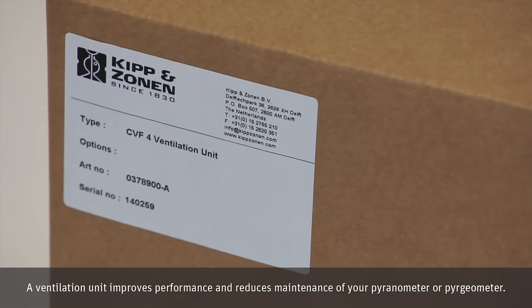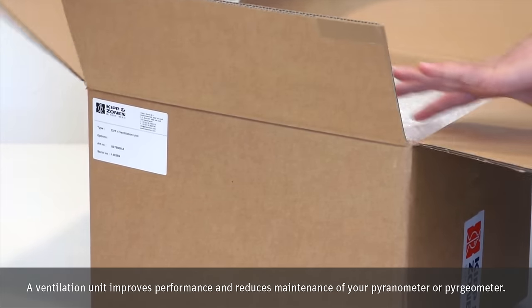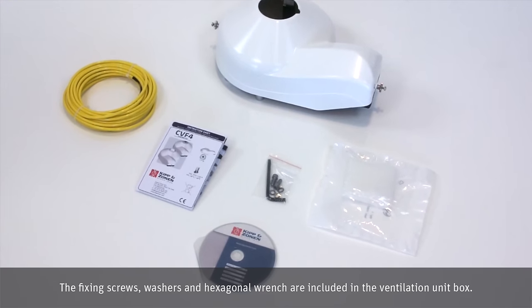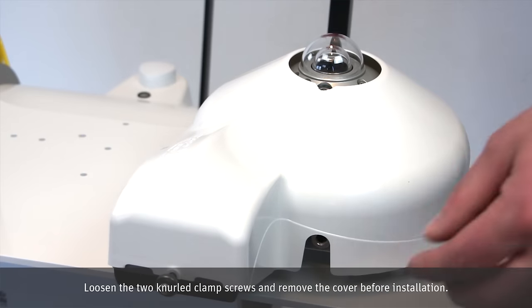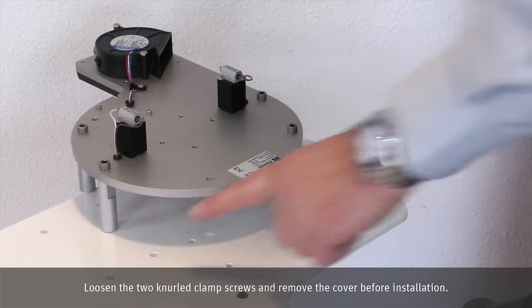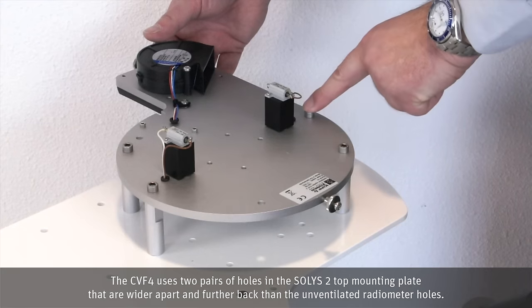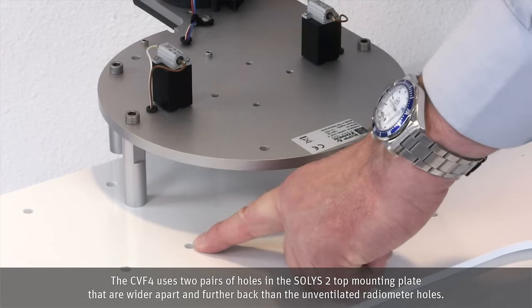The ventilation unit improves performance and reduces maintenance of your pyranometer or pyrgeometer. The fixing screws, washers and hexagonal wrench are included in the ventilation unit box. Loosen the two knurled clamp screws and remove the cover before installation. The CVF4 uses two pairs of holes in the SOLYS 2 top mounting plate that are wider apart and further back than the unventilated radiometer holes.